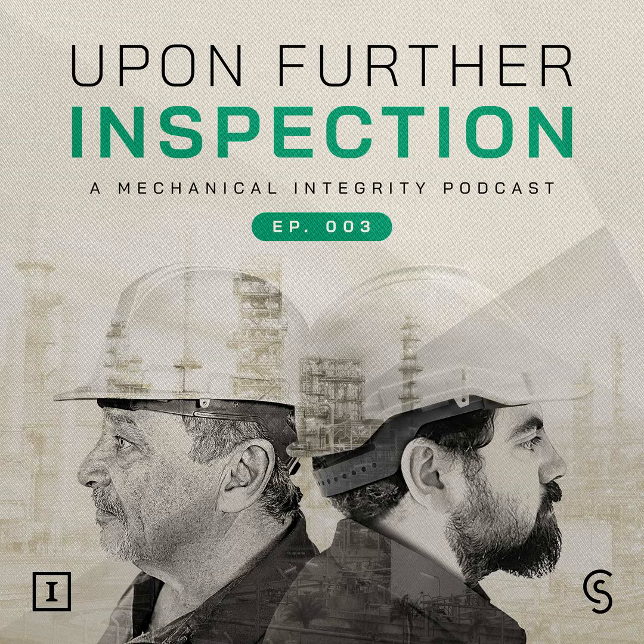So there was a lot of metallurgical lab work being done on taking cutout samples of suspected SSC and then doing Vickers microhardness testing across the thickness of the fracture area to look at where the hardnesses went. Typically you're looking at a Vickers hardness of less than 200 to be okay. If it was 200 or above, it was too brittle. But then that's where we got into too, understanding the importance of post-weld heat treatment on any welding that was done on this equipment.